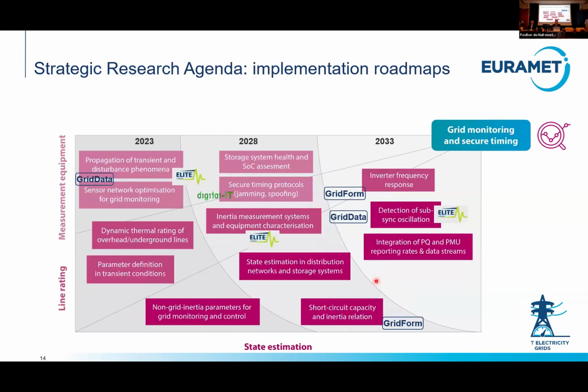So data analytics is strictly related to the monitoring of the grid. So here you see again a lot of challenges in this area related to the line rating, the state estimation, with the objective of optimizing the use of the grid. And also there's another big area on measurement equipment, how suitable they are for grid monitoring. And here again, we have projects coming up. All of these projects are very, very new: detecting new effects in the grid, characterization of the new features of the system, of extended frequency response of devices on the grid, another big area.